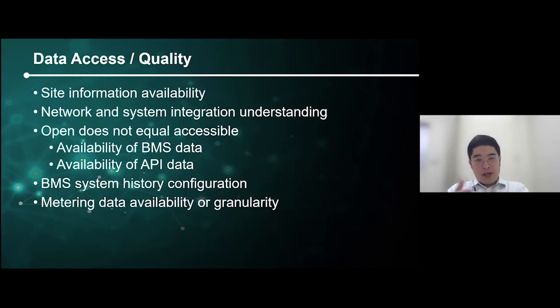The third point on data access and quality we came across was that open doesn't necessarily equate to accessible. Looking at BMS data points, all the controllers installed on site were BACnet compliant, open protocol controllers. However, BMS contractors still have a lot of flexibility to decide what points they expose on their platform. So while we expected certain points to be available through the gateways we installed, we eventually found that some points were not actually exposed. They were visible on the BMS, but we couldn't actually pull the same data points out of the system.